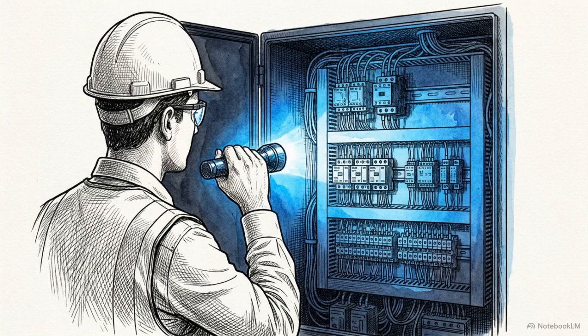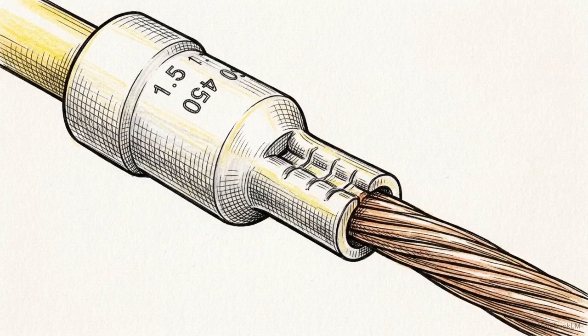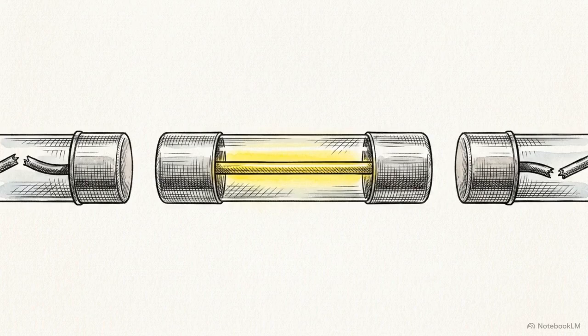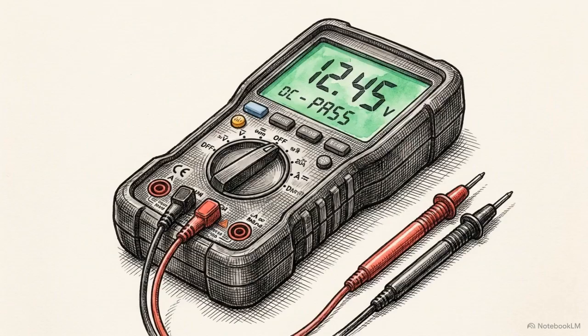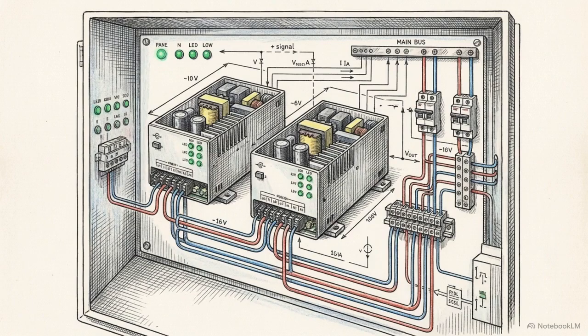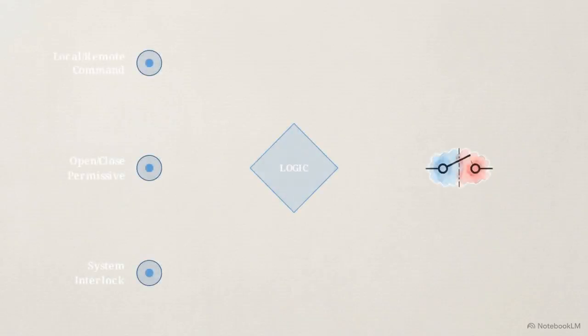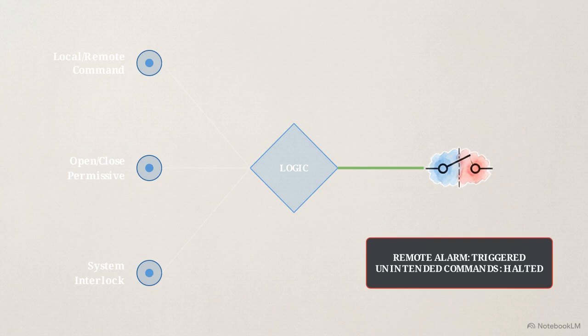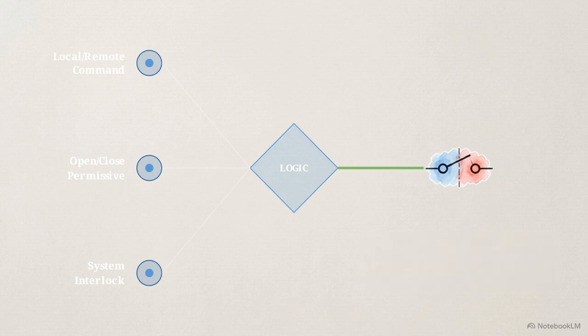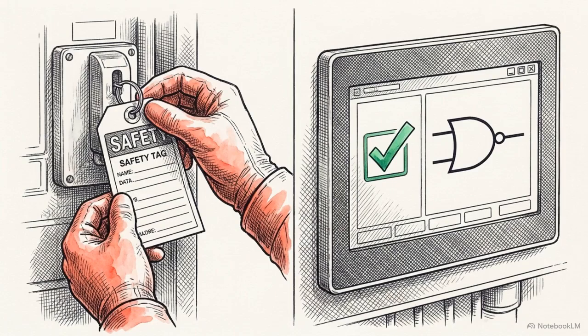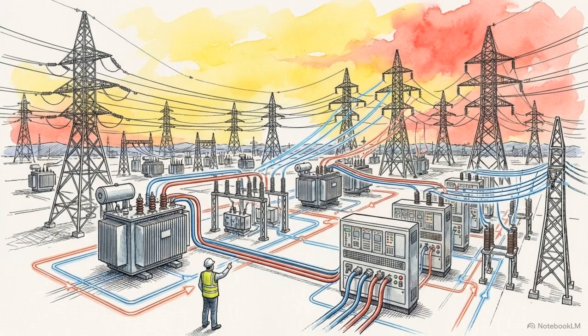Engineers check every single connection point. They verify ferrule labels, test terminal tightness, inspect intact fuses, and validate the integrity of both the DC and AC power supplies. This clears the path for the general scheme check. The objective here is to sequentially simulate required inputs, one by one. This confirms that every local or remote command, open or close permissive, and system interlock triggers the correct fail-safe response.